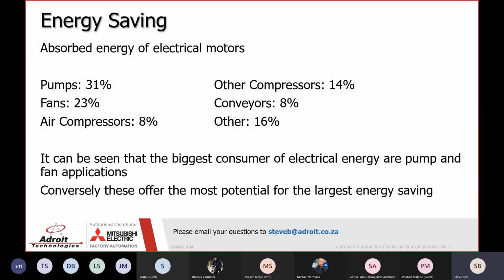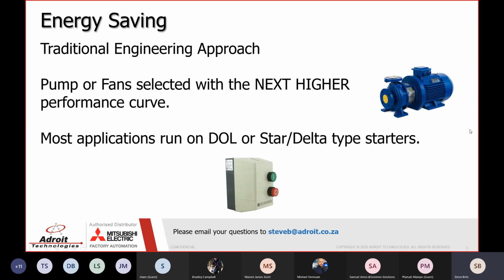It can be seen that the biggest consumers of electrical energy are pumps and fan applications. However, these will offer the largest energy saving possibilities as well. Traditionally, when you buy a pump or a fan, the engineers will use the next higher performance curve for your application to make sure that the pump will always meet the requirements that you have specified for your application. Most of the times these applications are run on direct on line or star delta types.